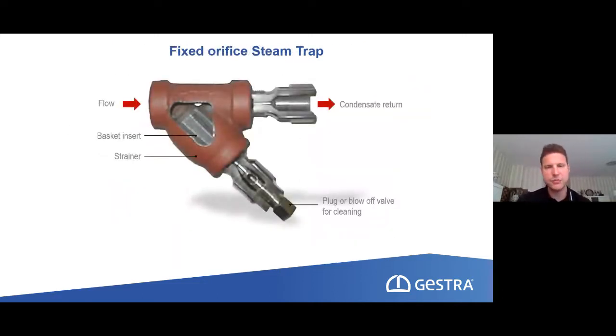So this is the last steam trap I'd like to speak about. It is the so-called fixed orifice steam trap. Fixed orifice steam traps are not this common, but they start to make their way inside steam businesses, but they have quite a lot of disadvantages. We'll figure that out when we think of the working principle.